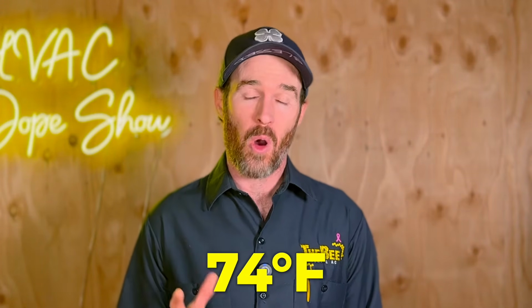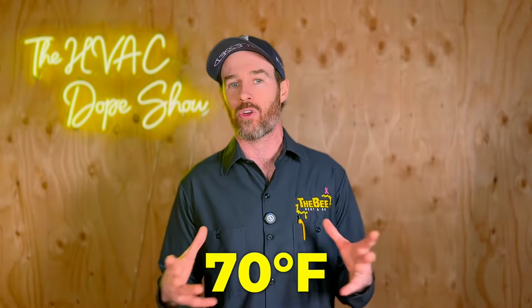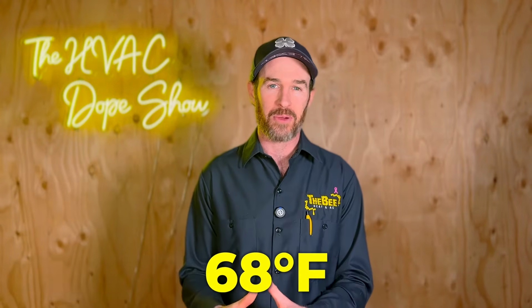Believe it or not, most systems are designed to hit a temperature between 72 and 78, depending on where you're located. So in Denver Metro, for example, our design parameters when builders are building a new home is to hit 74 degrees for most homes. So that's how they're designing the system. And most of the time, it'll get below that. It'll hit 70 degrees, or it'll hit 68 degrees if you like it really, really cold in your house.